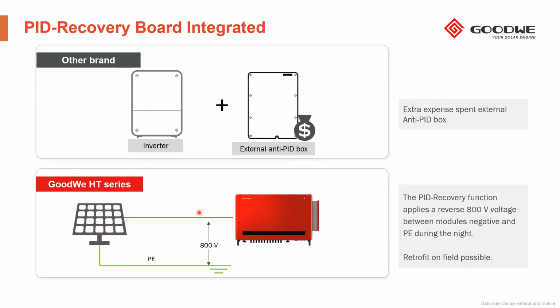We have a solution to revert the PID phenomenon. Basically, this phenomenon degrades the modules through a leakage current, a really tiny current from the most negative cells and modules to earth. The solution we provide, which is also common in the market, reverts this phenomenon and operates during the night. It can be applied in a retrofit way.